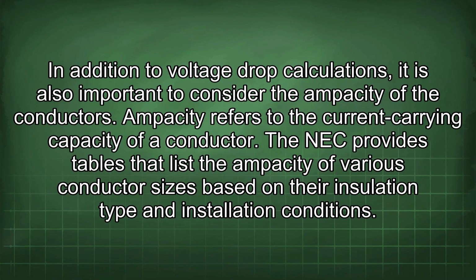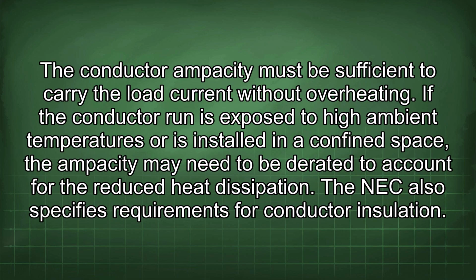In addition to voltage drop calculations, it is also important to consider the ampacity of the conductors. Ampacity refers to the current carrying capacity of a conductor. The NEC provides tables that list the ampacity of various conductor sizes based on their insulation type and installation conditions. The conductor ampacity must be sufficient to carry the load current without overheating. If the conductor run is exposed to high ambient temperatures or is installed in a confined space, the ampacity may need to be derated to account for the reduced heat dissipation.